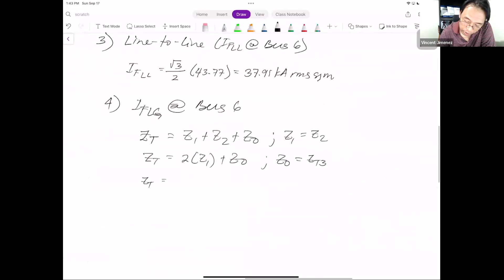Your Z1 at bus 6, computed earlier for the minimum fault, is 0.21 plus J3.29. That's Z1: 0.21 plus J3.29, times 2 since it's 2Z1. Then plus your Z0, which is equal to ZT3. Our ZT3 is 0.21 plus J2.29.